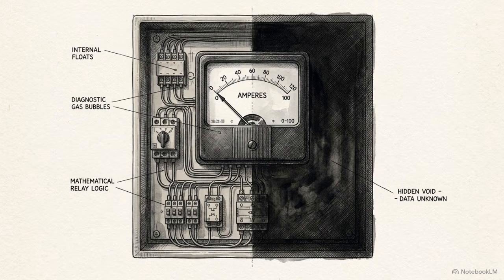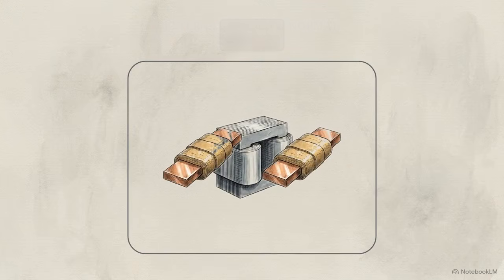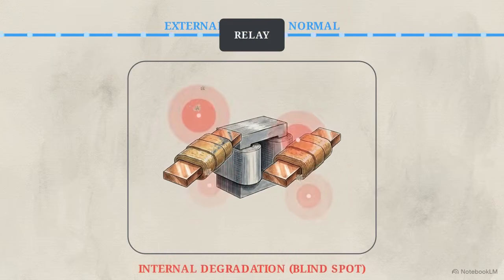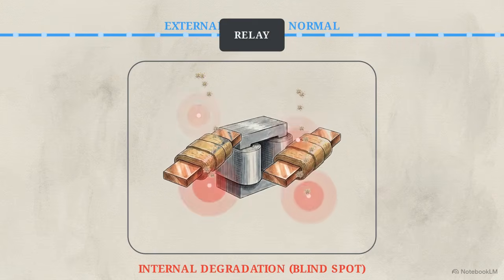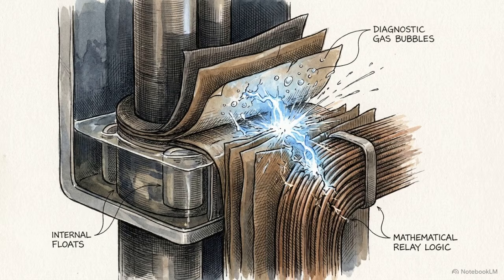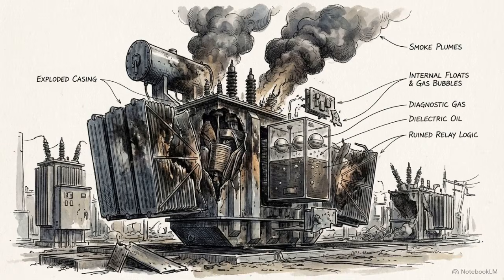But this purely electrical approach creates a massive blind spot. Because these relays only trip when current spikes, they are entirely blind to slow, low-magnitude degradation happening deep inside the insulation. If engineers wait for an internal short circuit to grow large enough to finally register on an external current monitor, it's too late. The damage is already catastrophic and uncontainable.